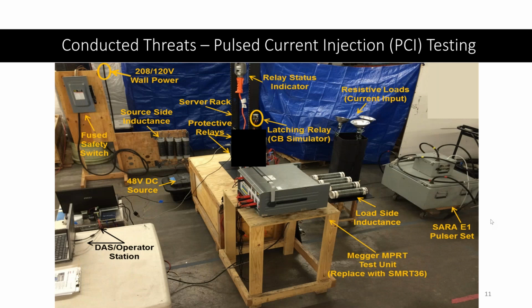Now we're getting to the part about what happens when that energy gets into the cable, and the simulation for that is what's called pulse current injection testing. This is a picture of that lab setup, and on the far right you see the pulsar. That is the one that will put energy into cables, which then go into the inputs of the device under test, which would be put in that black rack in the middle on the table.